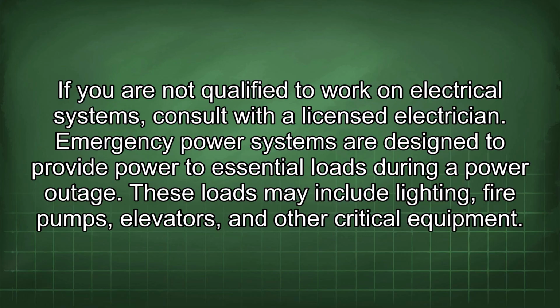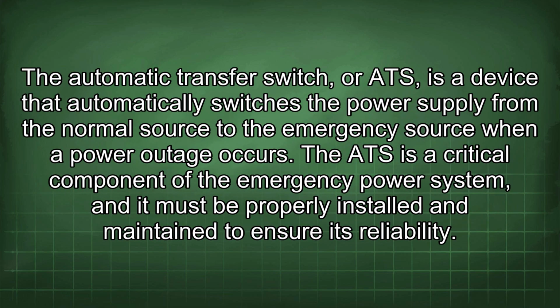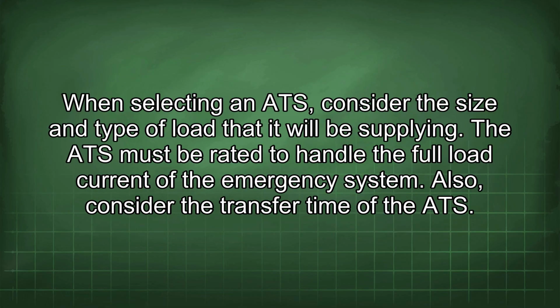Emergency power systems are designed to provide power to essential loads during a power outage. These loads may include lighting, fire pumps, elevators, and other critical equipment. The automatic transfer switch, or ATS, is a device that automatically switches the power supply from the normal source to the emergency source when a power outage occurs. The ATS is a critical component of the emergency power system, and it must be properly installed and maintained to ensure its reliability. When selecting an ATS, consider the size and type of load that it will be supplying.